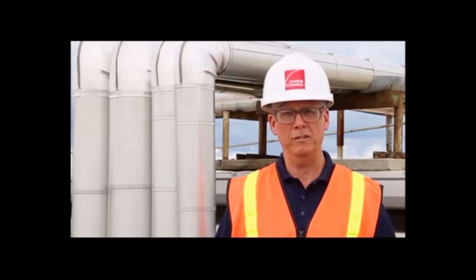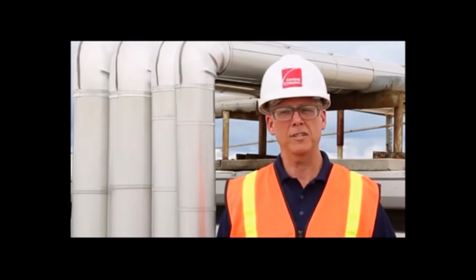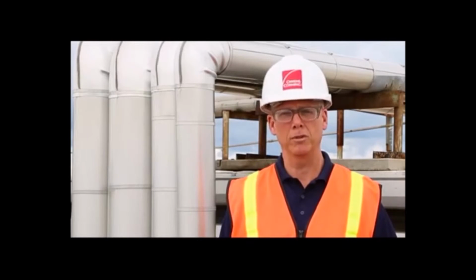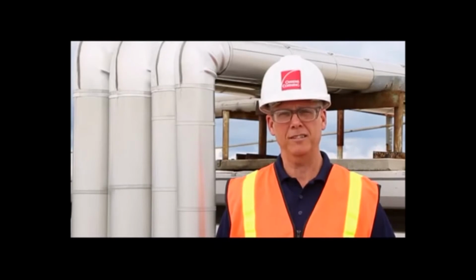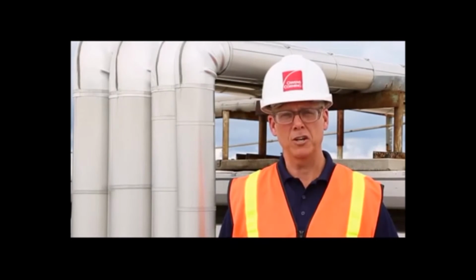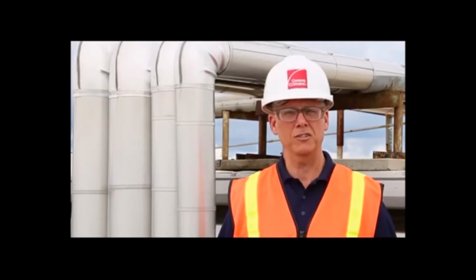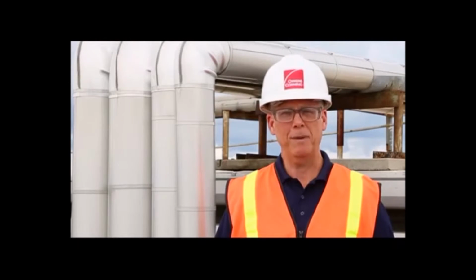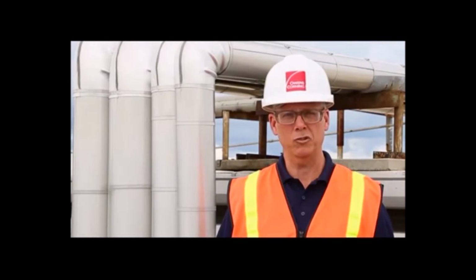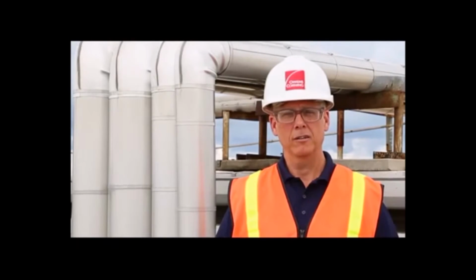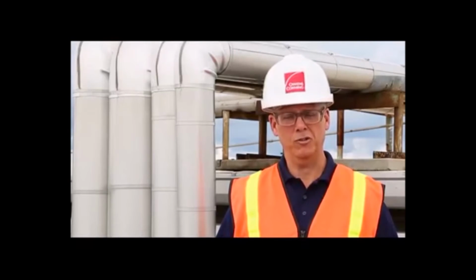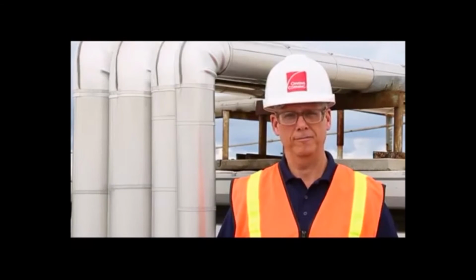You're exposed to the wind, the rain, the snow. You've got constant moisture drive because the system operates well below 0 degrees Fahrenheit. Although there is a vapor barrier and jacketing that protects the insulation, over time it deteriorates. And when it deteriorates, the insulation is exposed to those elements. Expanded polystyrene will collect that moisture between the beads. It'll turn to ice and it'll reduce the R value. Extruded polystyrene doesn't collect the moisture, resists the moisture, and in fact will maintain its R value.